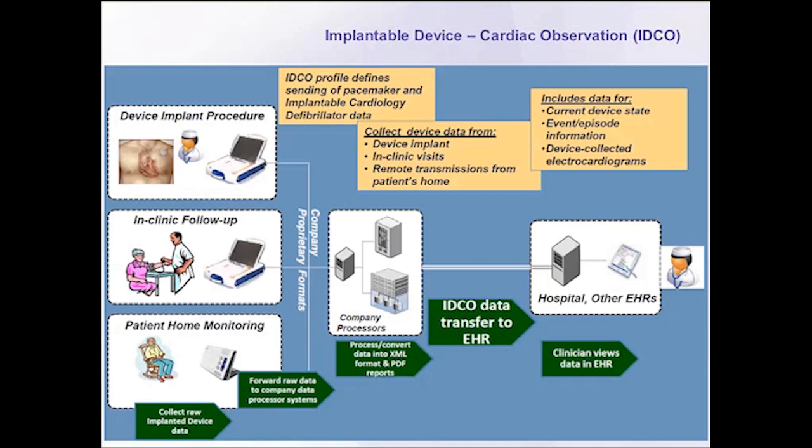Implantable device cardiac observation. Think of it as the DEC profile from earlier slide, except we're extending this to support implantable devices, which may not have enough communications capability or may report using other data transports or syntax, and gatewaying that to a format such that it's consistent with all the other PCD profiles.